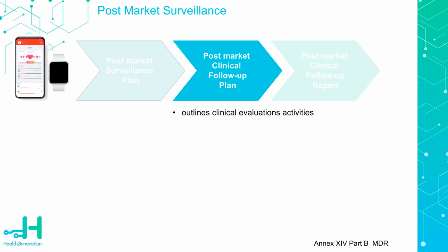Not all devices may require one. However, a justification for why it is not applicable must be included in your technical documentation to explain why it is not done. You will still need to have a PMS plan, however.